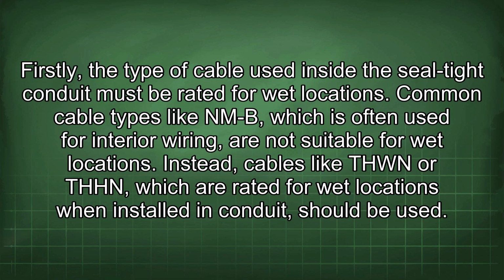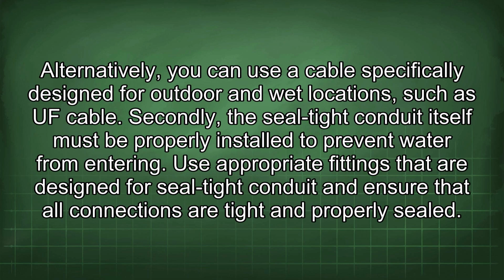Firstly, the type of cable used inside the seal-tight conduit must be rated for wet locations. Common cable types like NMB, which is often used for interior wiring, are not suitable for wet locations. Instead, cables like THWN or THHN, which are rated for wet locations when installed in conduit, should be used. Alternatively, you can use a cable specifically designed for outdoor and wet locations, such as UF cable.